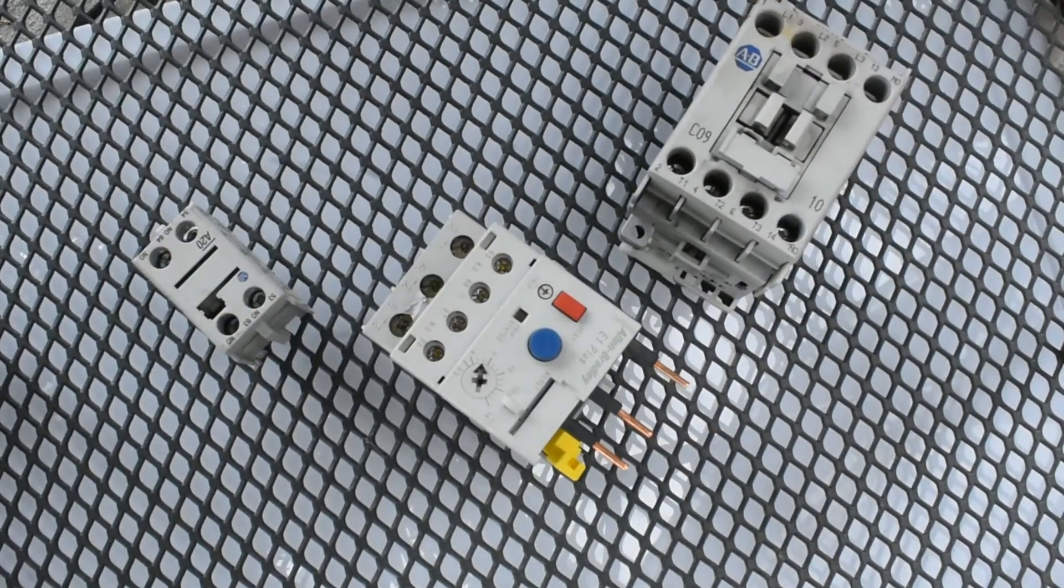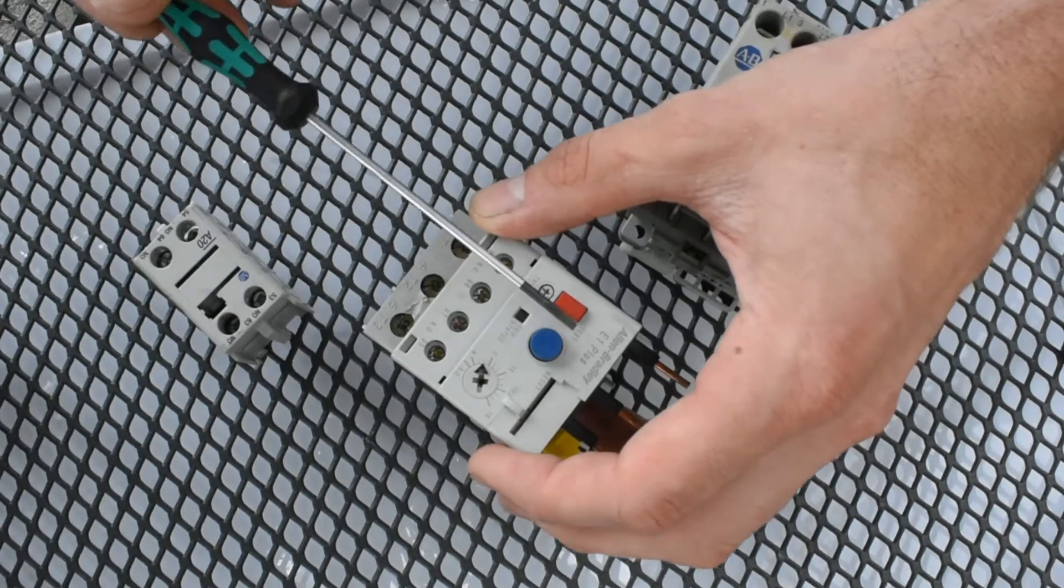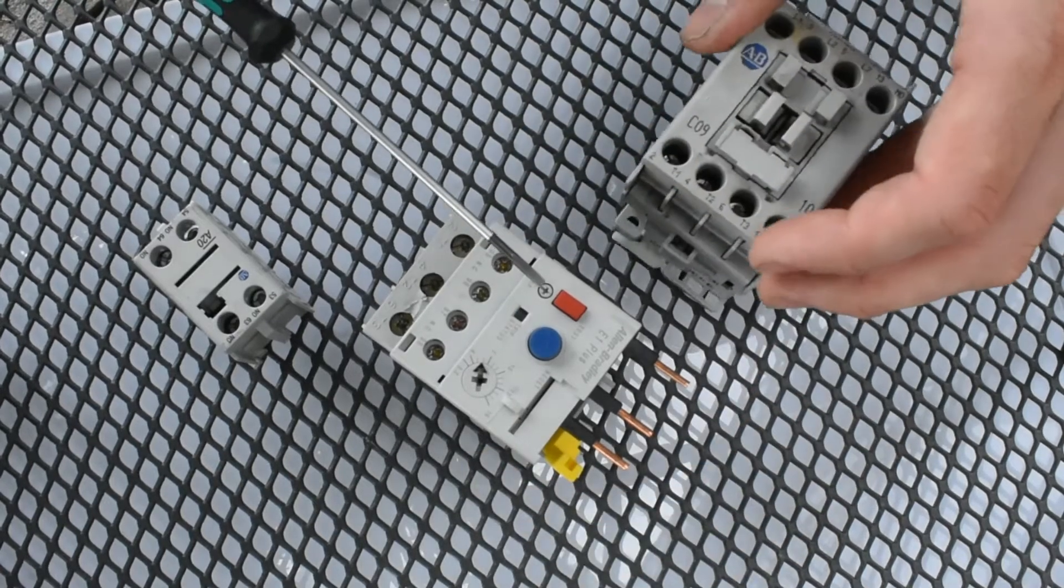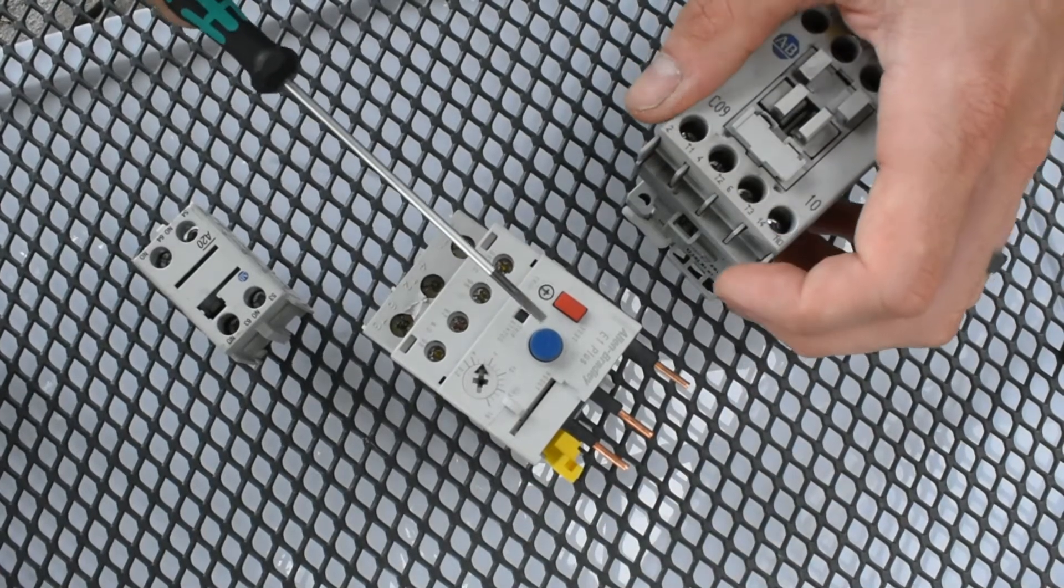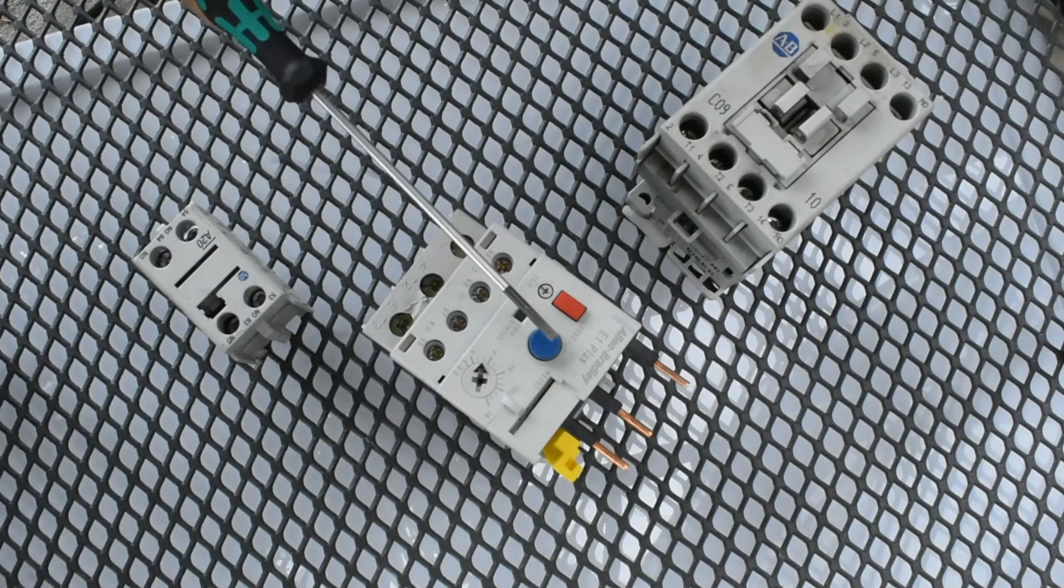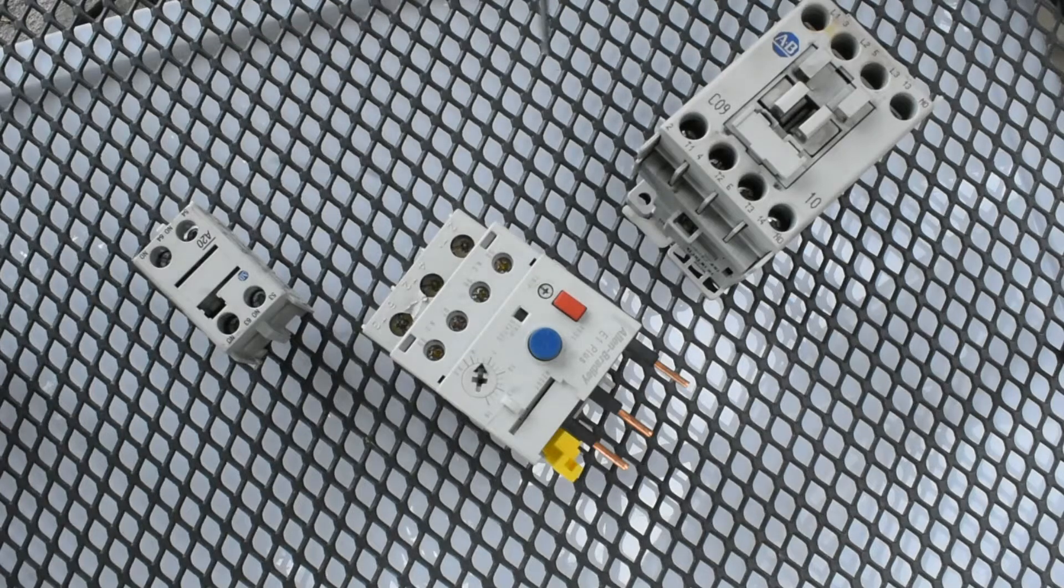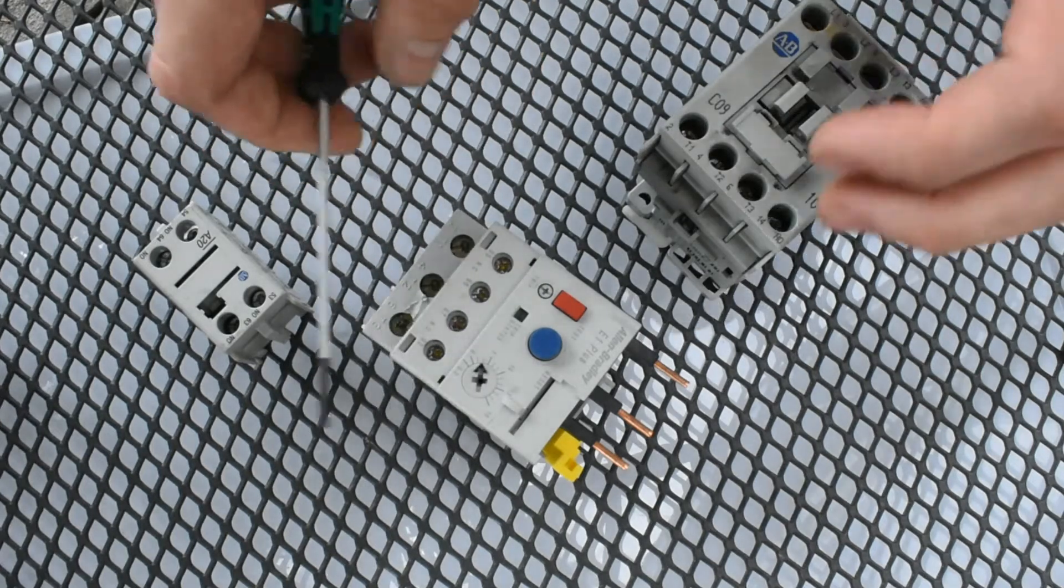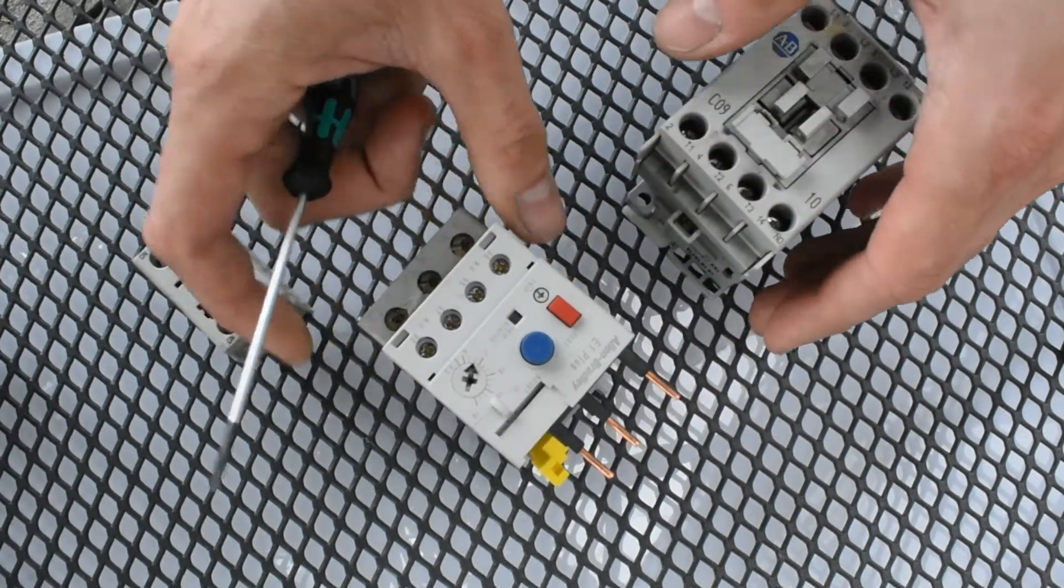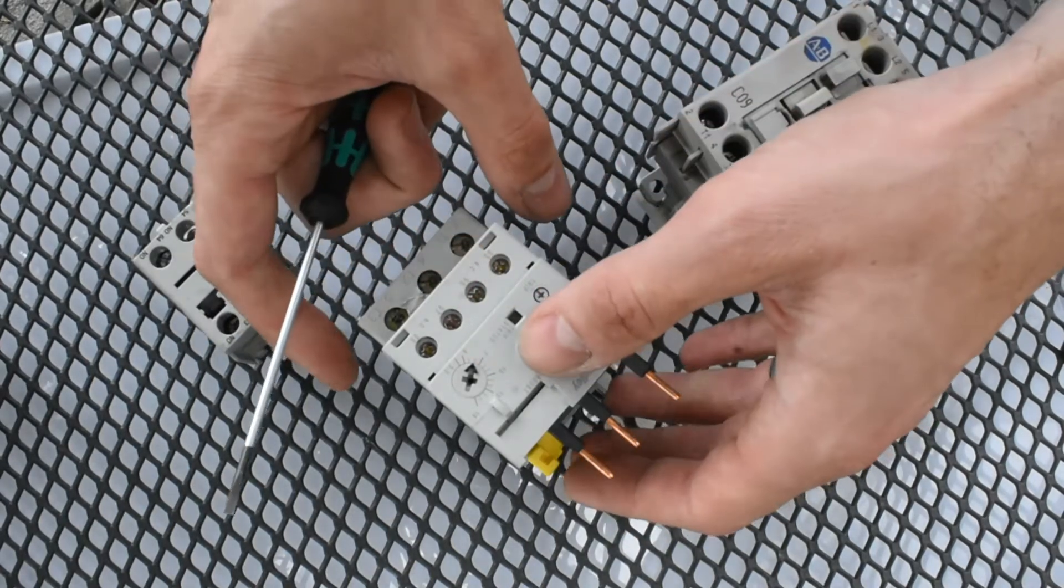Now, this other device, this overload relay, is a really important part of the motor starting system. It has a test and a reset, so that you can periodically test to make sure that the metallic contacts inside are effectively opening and closing. But basically, its job is to protect the motor and turn itself off in case of overcurrent. That overcurrent might come from too much force and load on the motor, and there's a couple of different reasons that we want to protect that, but certainly safety to the system and protection of the circuitry and the load is the most important.